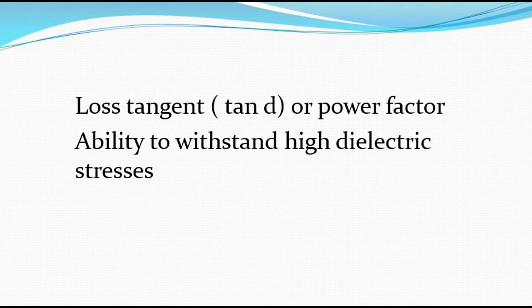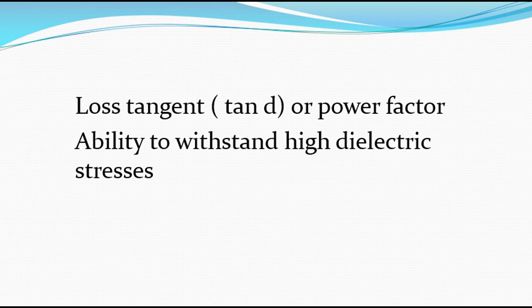Another one is loss tangent — you can also call it power factor. All these things that I am mentioning here are the essential aspects of the performance of dielectric liquid. Loss tangent or power factor is very important as well. It also has the ability to withstand dielectric stress.